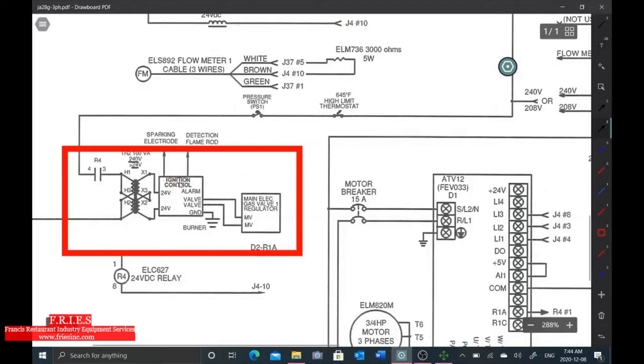How this module resets is you have to lose power to the module. Once this module loses power, okay, it will reset and it will try for ignition. So every couple minutes, this motor will stop running and it'll change rotations. As soon as that happens, this pressure switch opens. Once this pressure switch is open, we have now lost our 24 volts to this module. Once that pressure switch opens, we have now lost power to our transformer. Once you lose power to your transformer, you no longer have voltage going to the module, and that's how it resets. So every couple minutes, this module resets from the blower motor going in the opposite direction.